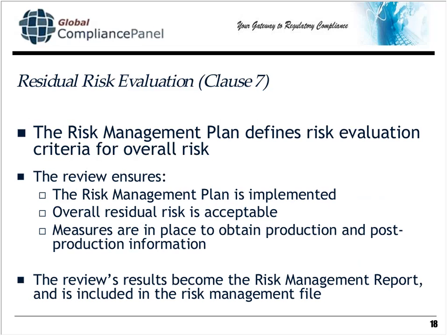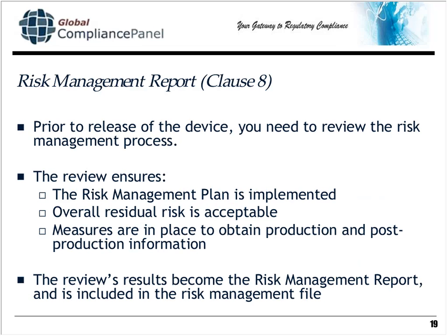Then finally, in Clause 8, I've been through all of this activity. I've identified all of the hazards, estimated the risk, done all of the risk reduction, evaluated overall residual risk, and now I'm going to say, am I done? Have I done everything that I was supposed to do? Have I followed the risk management plan? And are the subsequent activities in place and ready to go?